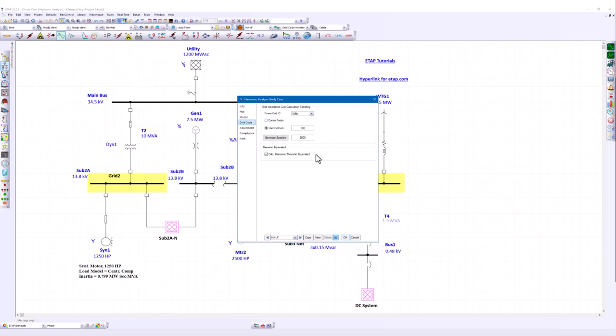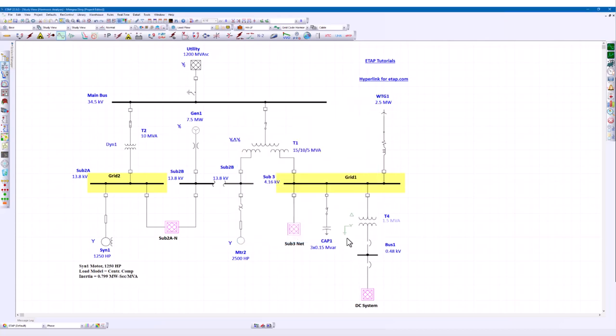We provided the option to calculate the harmonic Thevenin equivalent as well. You can check it in the study case if that's needed. Another tab to set is for the plot page. Make sure that you select the utility connected bus ID in the plot list, which is my main bus here. The other tab settings are just the same as the normal harmonic evaluation study types. After the study case is set up, you can go to the harmonic right toolbar and click on Run Grid Code Harmonics. It will start all the automatic calculation.